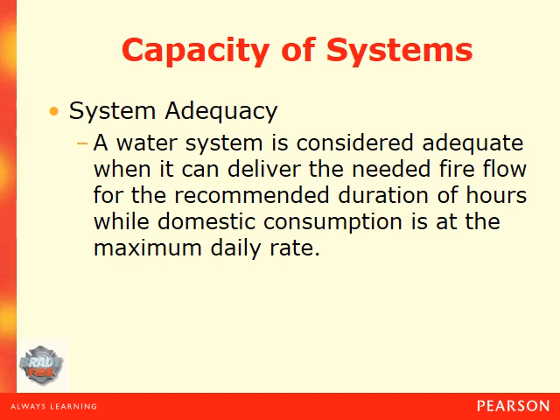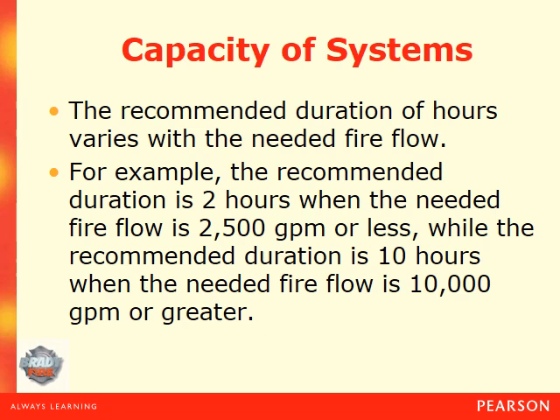A water system is considered adequate when it can deliver the needed fire flow for the recommended duration of hours while domestic consumption is at the maximum daily rate. The recommended duration of hours varies with the needed fire flow. For example, the recommended duration is two hours when the needed fire flow is 2,500 gallons per minute or less, while it is 10 hours when the needed fire flow is 10,000 GPM or greater.